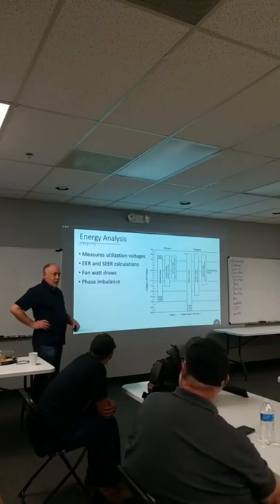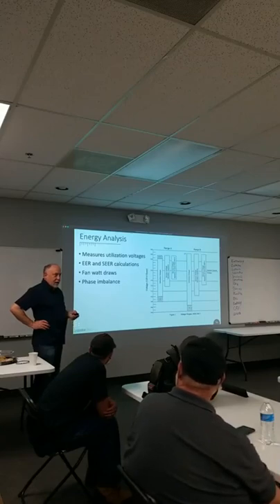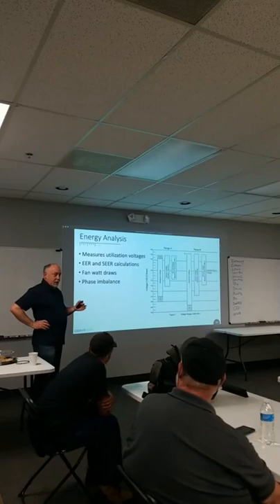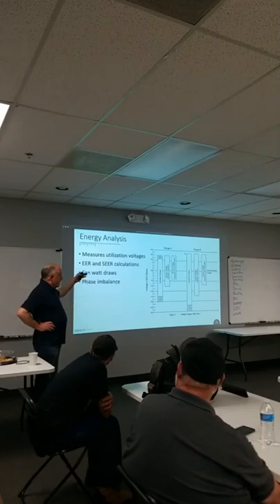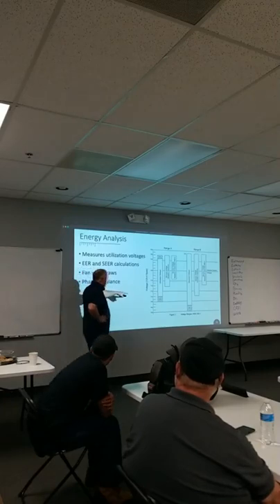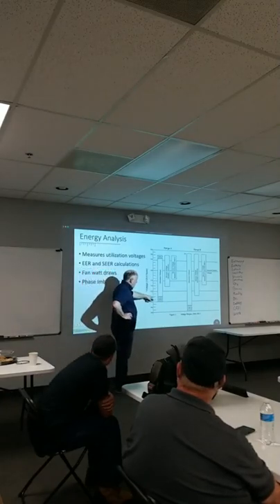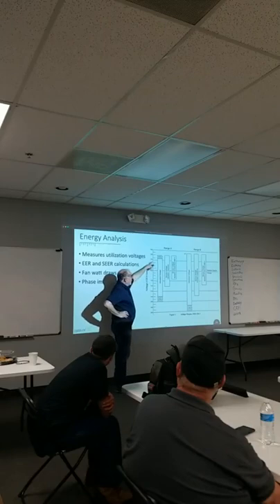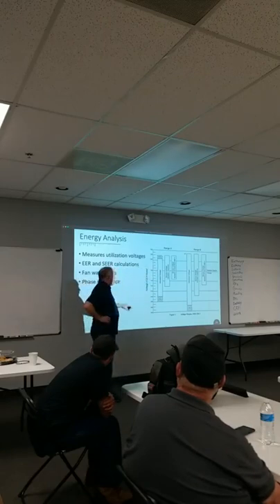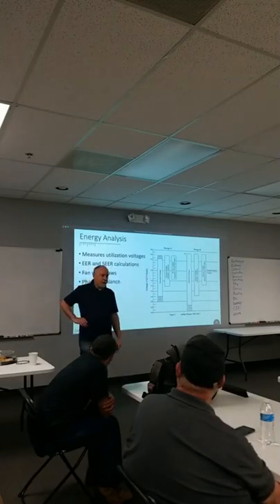Remember, voltage is electrical pressure. So you never want to test a voltage when the machine is off, unless you want to get your service voltage, and it'll be right up there. But when it starts, there's an allowable voltage drop of about 3% in the line. When you test initially, we have to make sure we're on the correct utilization range, so a 110 volt circuit could be as little as 110 volts, and it could be as high as 126, 125 volts, 124.5 volts, and it's totally fine, right?